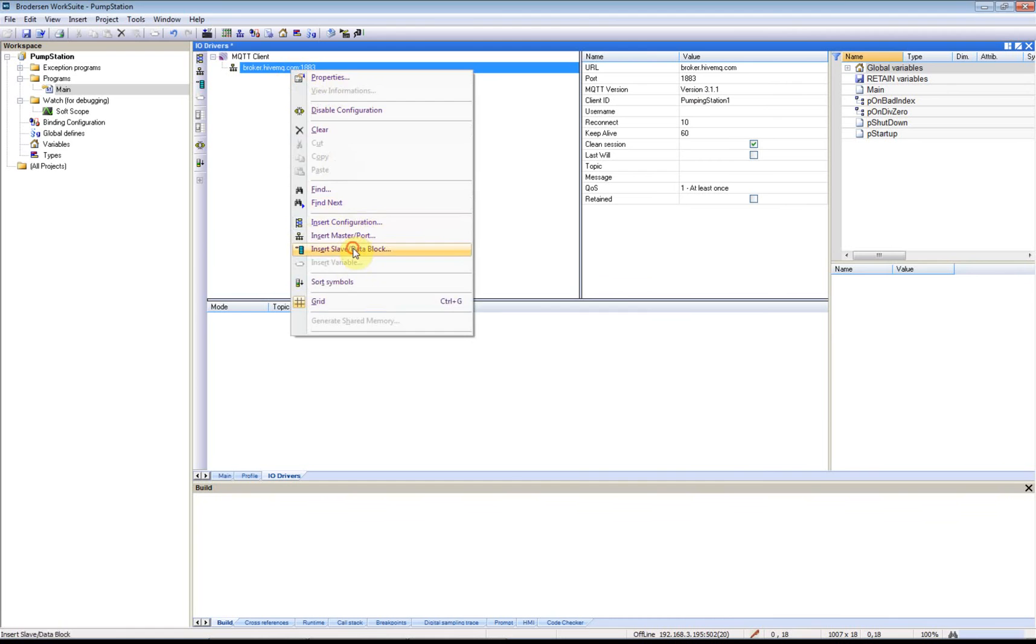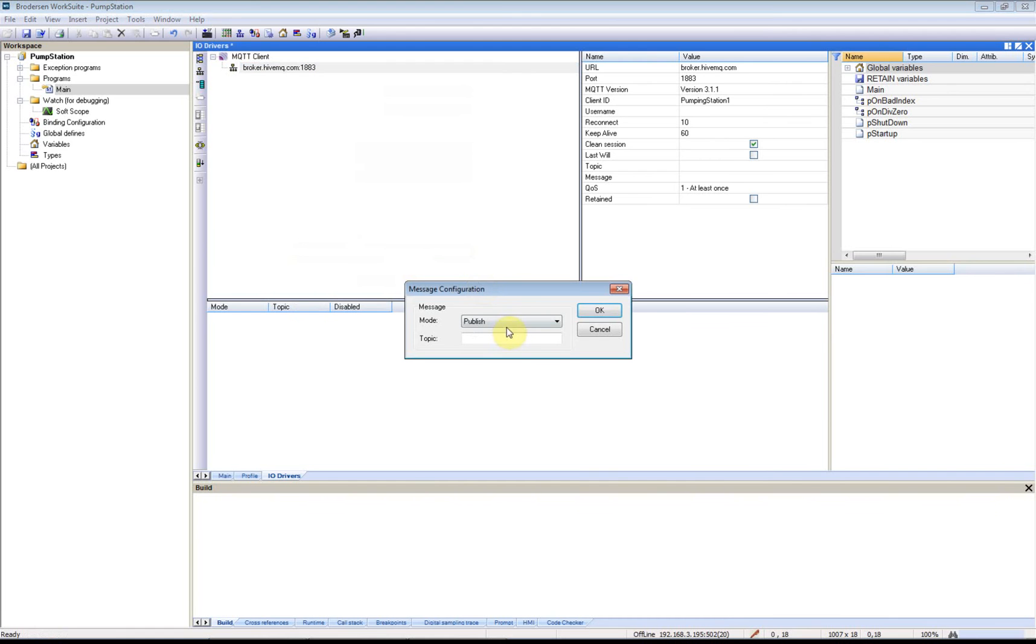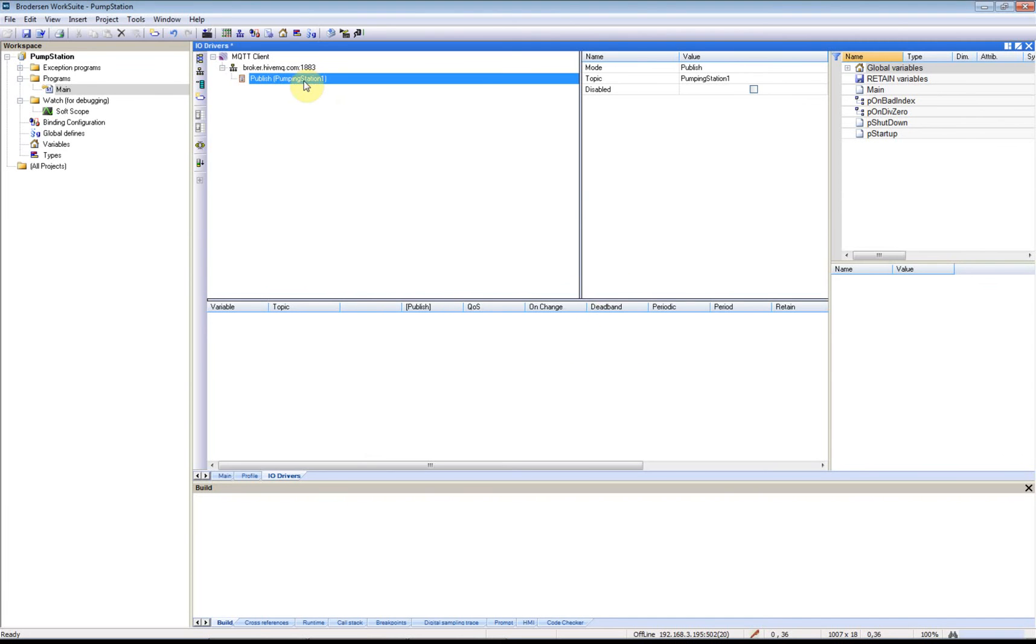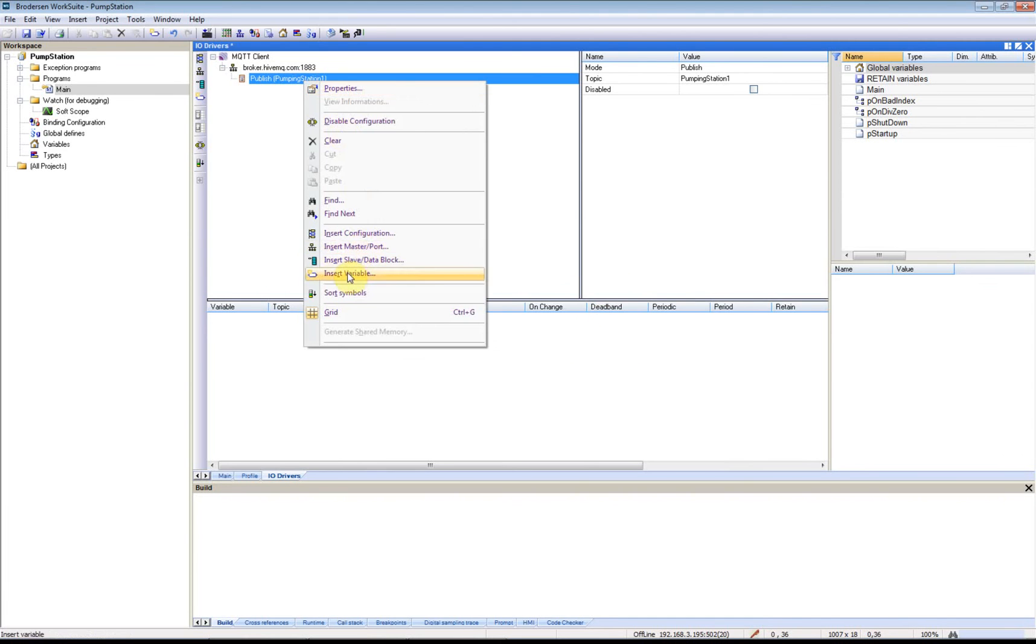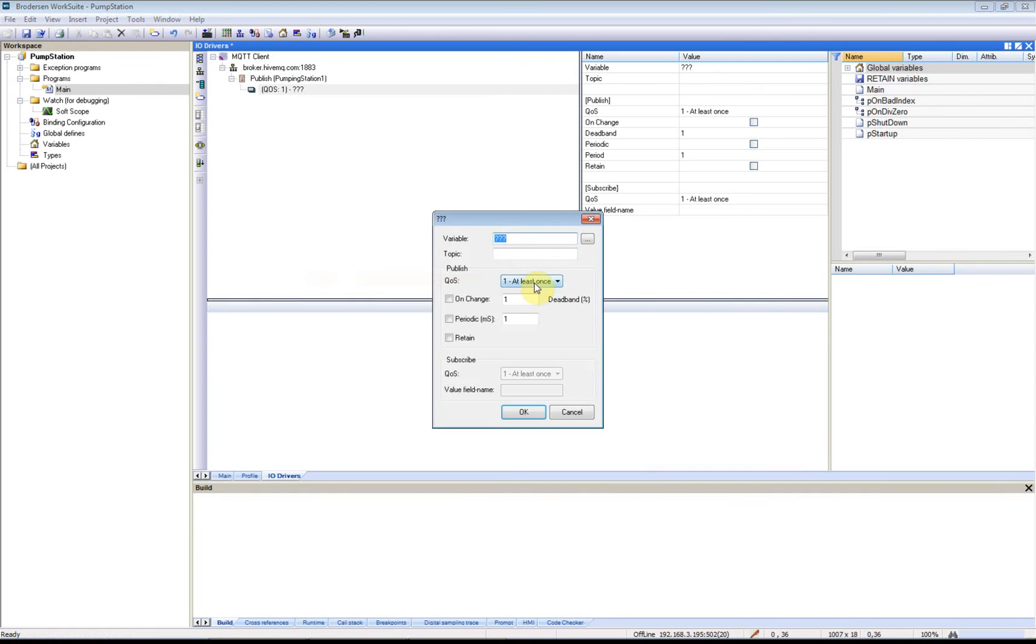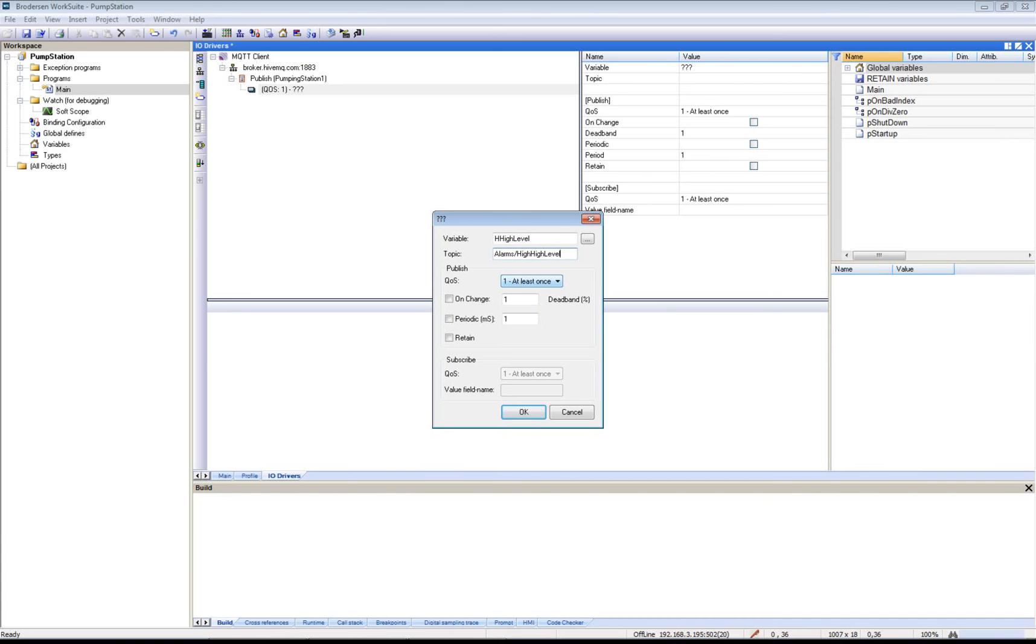Now I'll start by adding my events that I will publish to the MQTT broker. The topic will be PumpingStation1. First I'll add all our alarm signals. I have one for High High Level. I will put it in the topic Alarms and then High High Level, so when this digital input changes. I'll add one for our High Level.